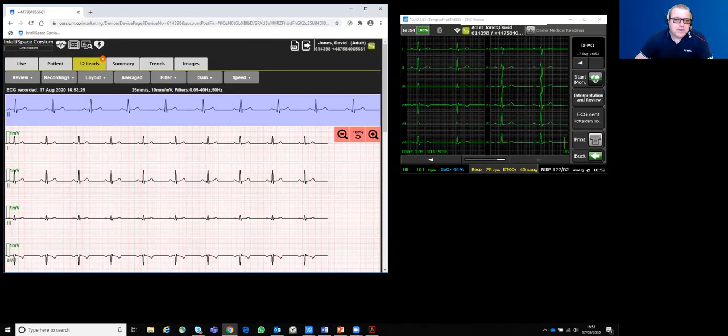You can average the complex, you can remove filters, you can change the gain size or the display speed of the ECG. Additional 12 leads can be viewed to get historical comparisons. And when ready, the ECG can be reviewed.